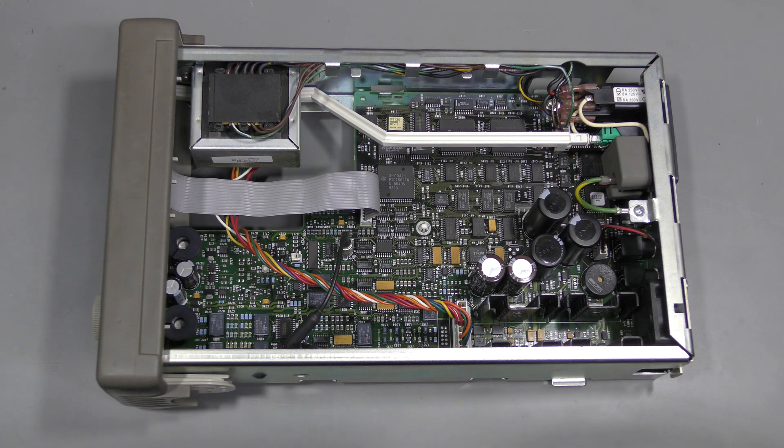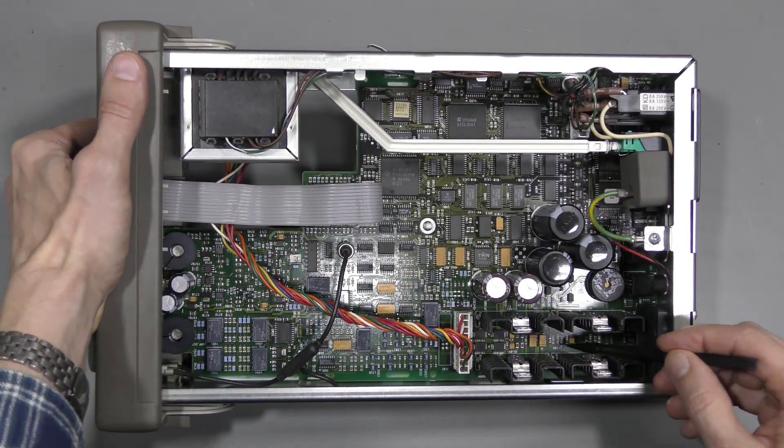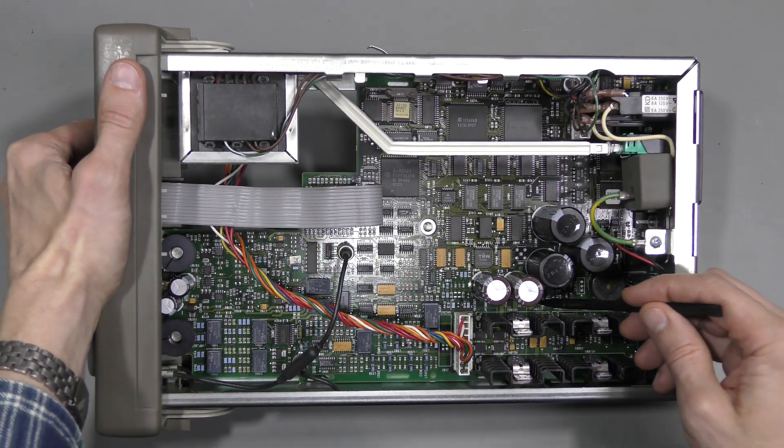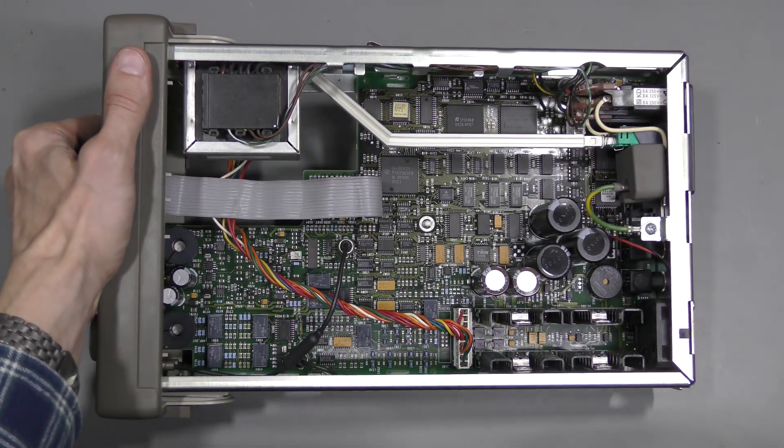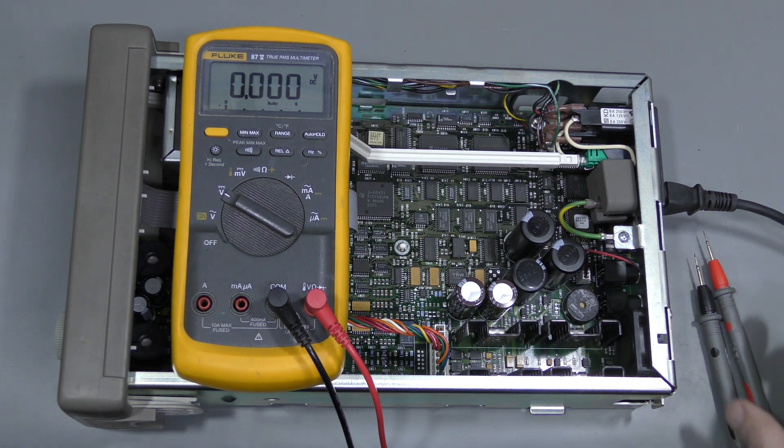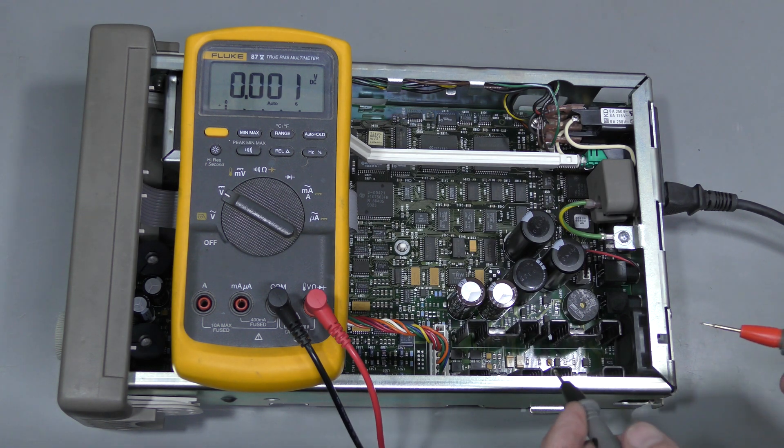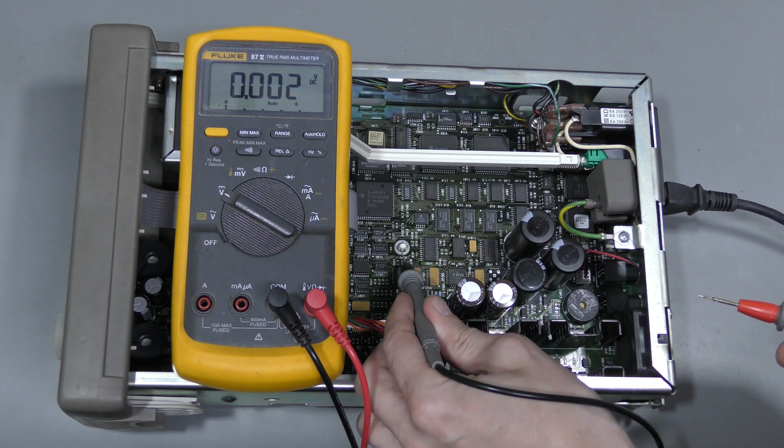Here we are inside and nothing is obviously wrong. High quality build as expected. The first thing is to check voltages, of course. Here I see some markings on the board: a plus 5V rail here, plus and minus 18 and minus 5.2. Let's check. I doubt that the problem is with power rails because the unit is mostly working, but this should be checked first as a matter of course anyway.